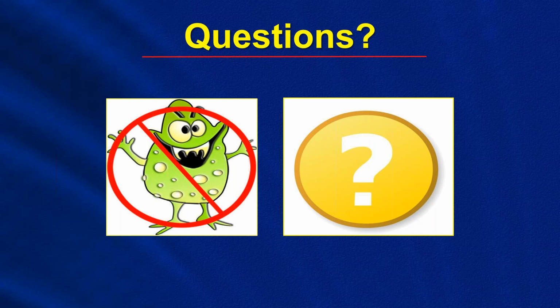Each manufacturer of ATP testing devices will tell you the acceptable number, based on independent research. As long as your reading is below that threshold, it's acceptable and doesn't need to be recleaned. For example, if the acceptable number is 100 RLUs or below and you get 65, that's fine. You're setting a parameter for when ATP levels are too high, indicating the need to reclean and reprocess the instruments or scopes. You rarely get a 0, but low numbers like 2, 4, 5, 7, 10, or 12 are more than acceptable.